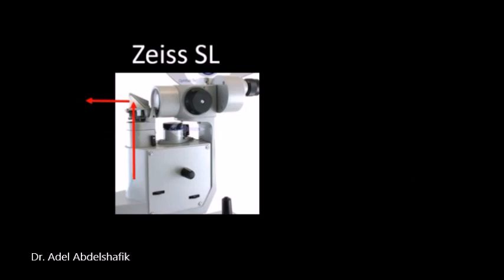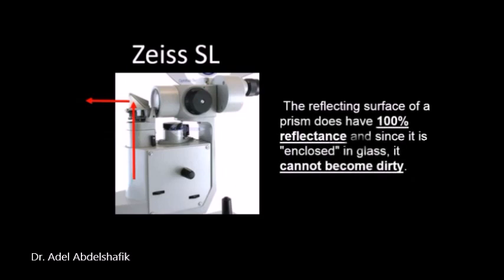In Zeiss slit lamp using a prism, light emitted from a lamp is reflected 90 degrees into the patient's eye. The reflecting surface of the prism does have 100% reflectance and since it is enclosed in glass it cannot become dirty. On the other hand, mirrors are fragile and are more susceptible to deposition of debris.